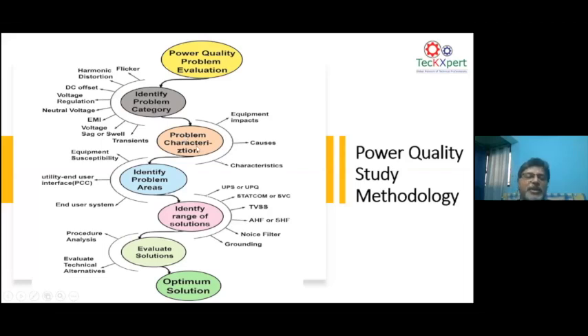When I say characterize the neutral ground voltage, you can capture the voltage waveform, take the magnitude, and decide the duration. That is how you characterize. For example, if you want to characterize harmonics, you look at what the frequency is, what the magnitude is, and what the duration is, whether it is odd harmonic or even harmonic. You find out the cause and how it is impacting the equipment. So when you use a power quality analyzer, you should be able to identify the problem, characterize the problem, identify the areas where the problems are, and accordingly give the right solution.